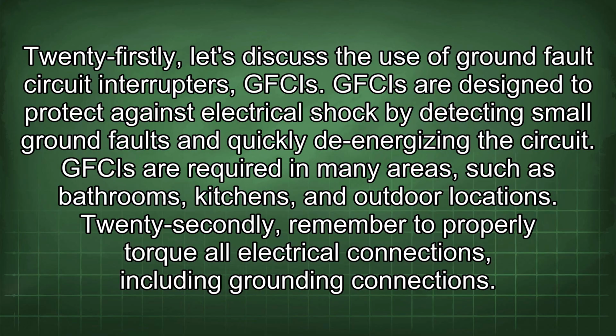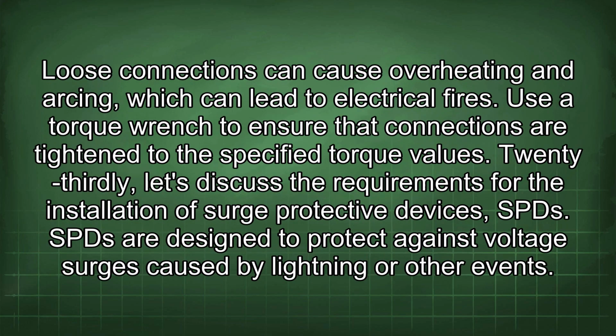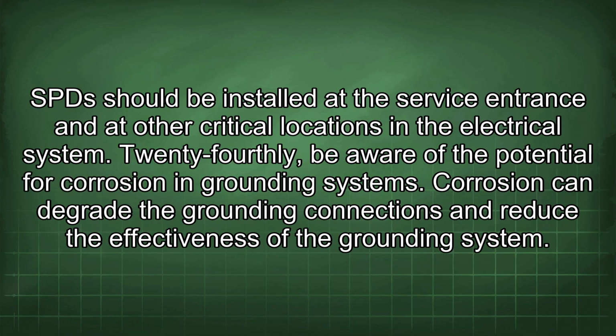22ndly, remember to properly torque all electrical connections, including grounding connections. Loose connections can cause overheating and arcing, which can lead to electrical fires. Use a torque wrench to ensure that connections are tightened to the specified torque values. 23rdly, let's discuss the requirements for the installation of surge protective devices, SPDs. SPDs are designed to protect against voltage surges caused by lightning or other events. SPDs should be installed at the service entrance and at other critical locations in the electrical system.